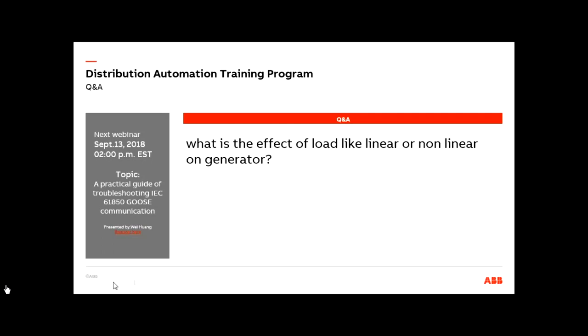I don't know what exactly is meant by the effect of load. Loading of a generator can create an unbalanced situation. Unbalanced loading of the generator is not good because, as we saw, the unbalance of loads can create negative sequence currents, which is not good for the machine. So if it is a balanced load situation, it won't affect the generator as much.